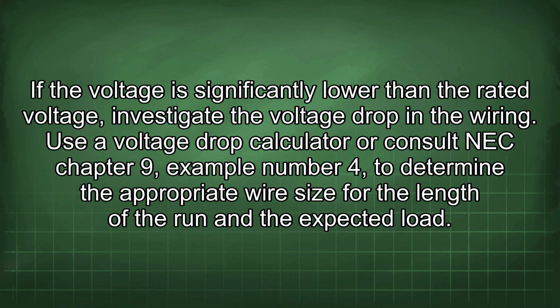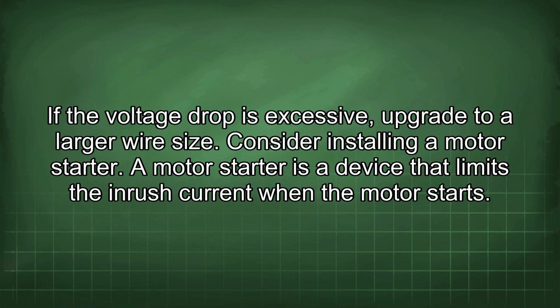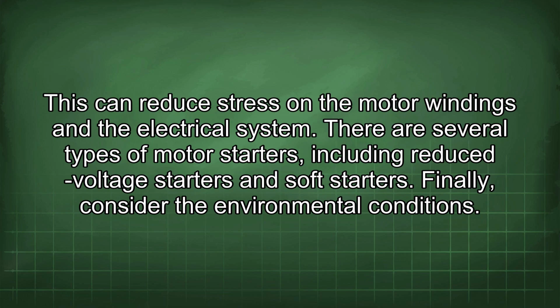Use a voltage drop calculator or consult NEC Chapter 9, Example Number 4, to determine the appropriate wire size for the length of the run and the expected load. If the voltage drop is excessive, upgrade to a larger wire size. Consider installing a motor starter. A motor starter is a device that limits the inrush current when the motor starts. This can reduce stress on the motor windings and the electrical system. There are several types of motor starters, including reduced voltage starters and soft starters. Finally, consider the environmental conditions.